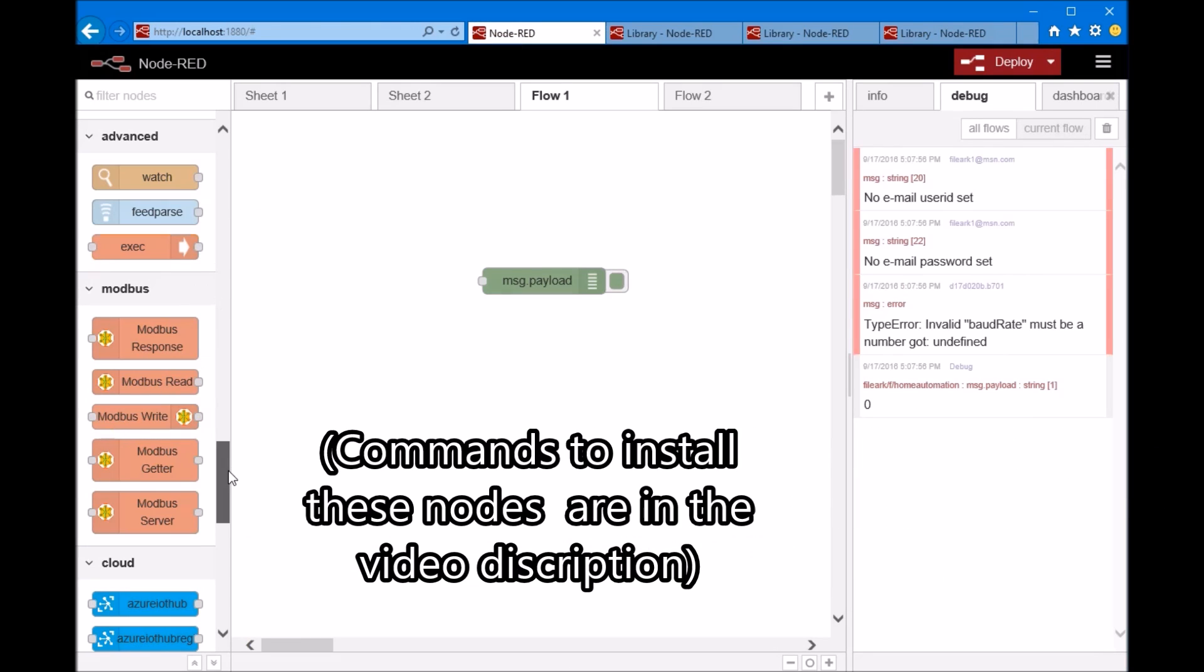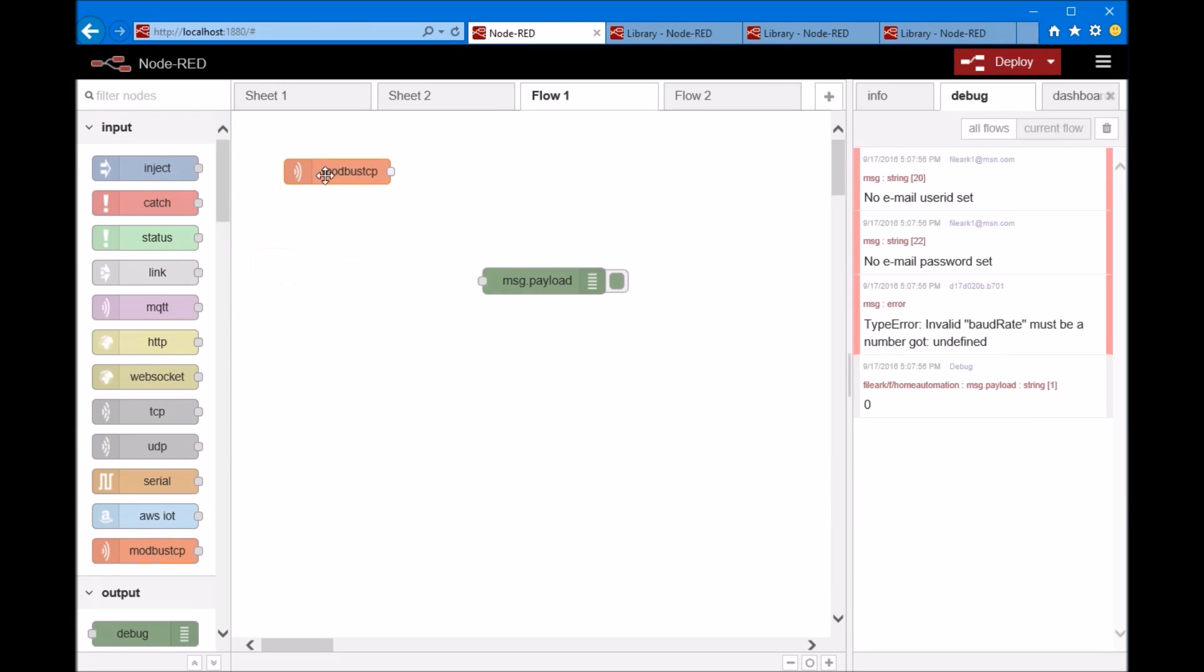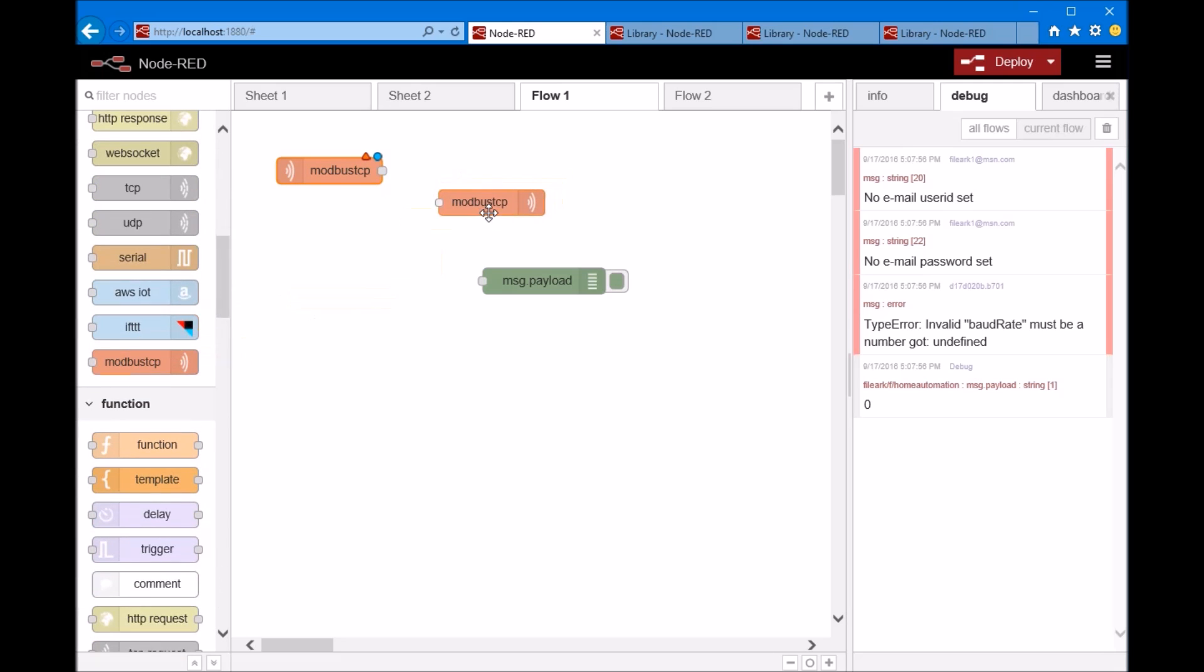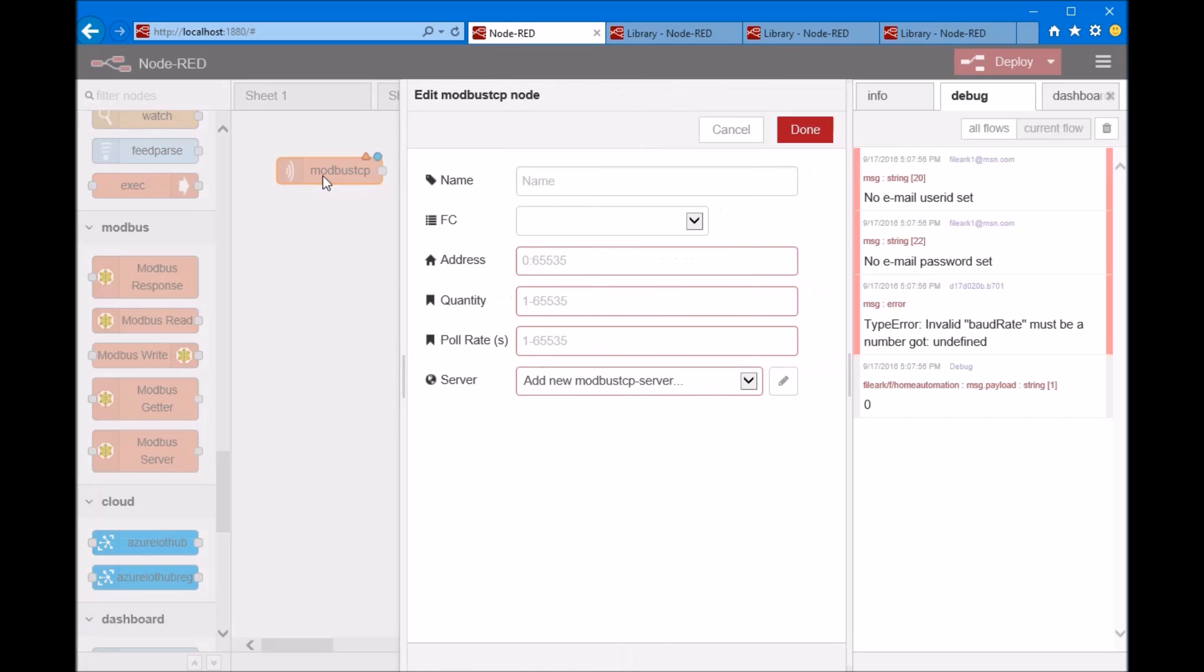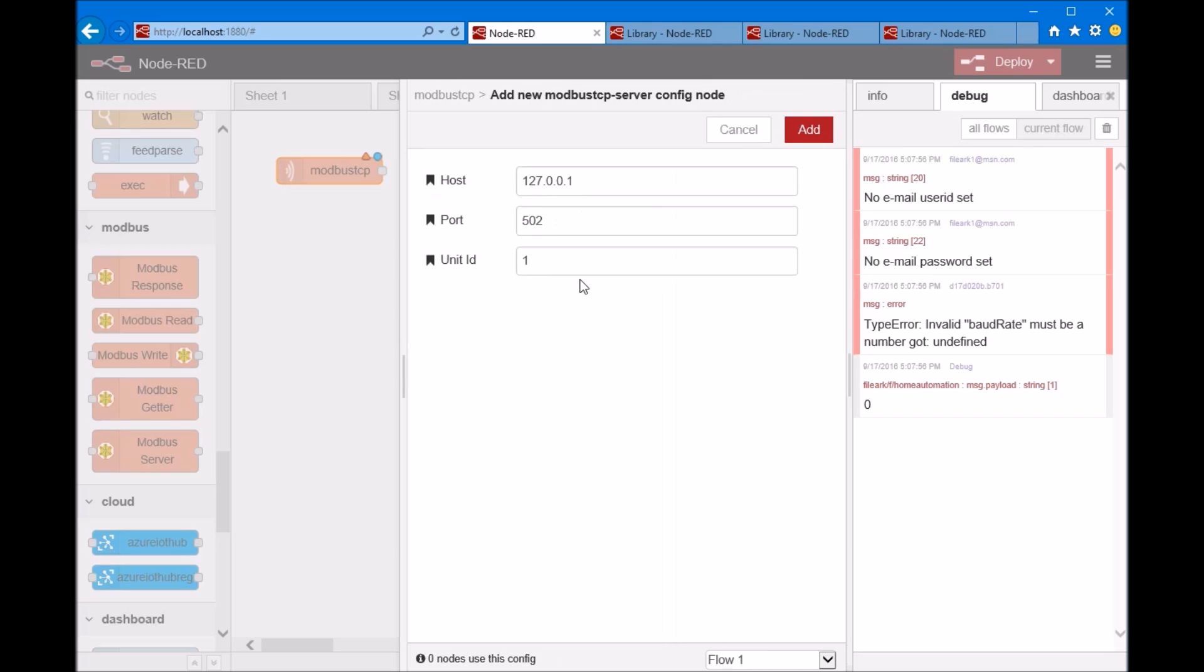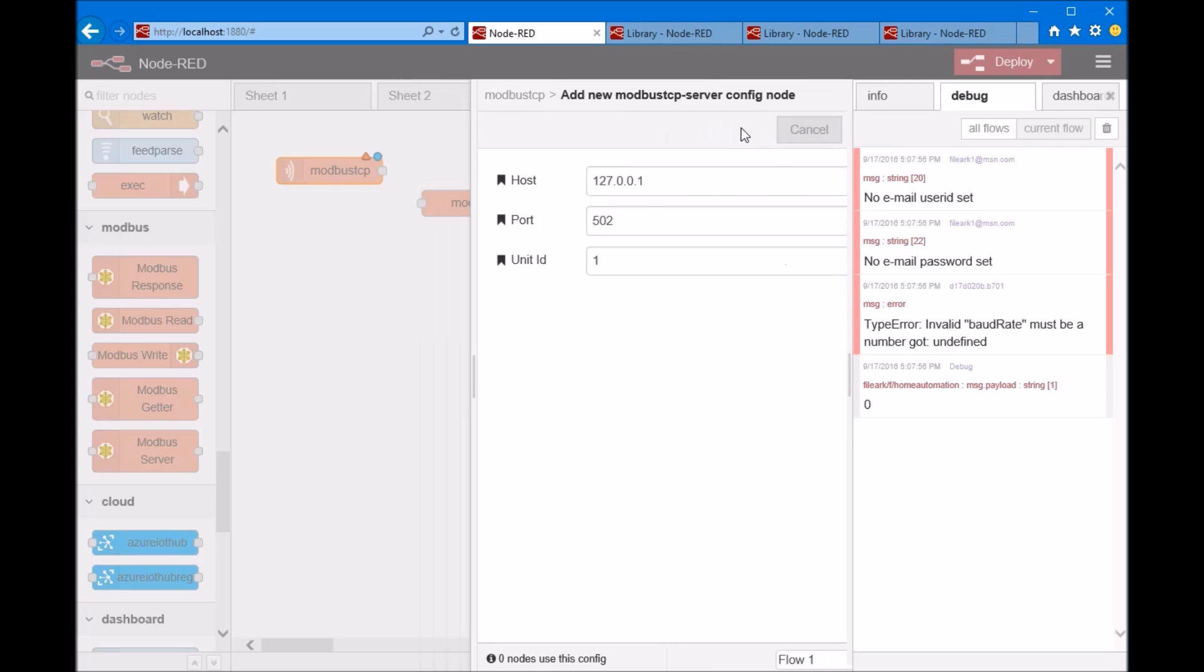So once you have these installed, you'll see Modbus TCP in and out. Looking at Modbus TCP, it's pretty straightforward. You go ahead and pick your Modbus command, put in your address, poll rate, and then you can go ahead and add a server, IP address, and port. So that's pretty straightforward right there.